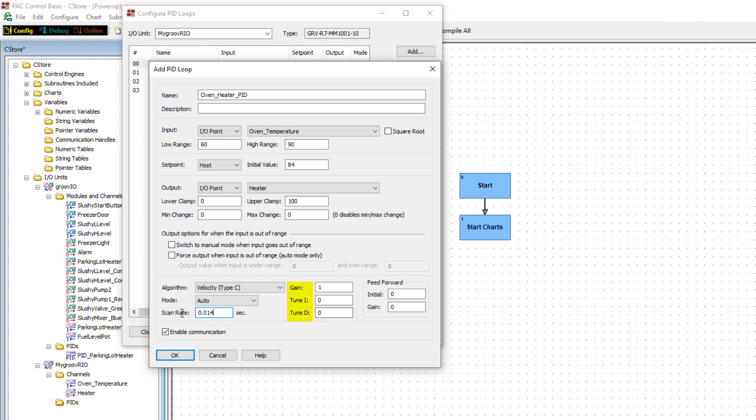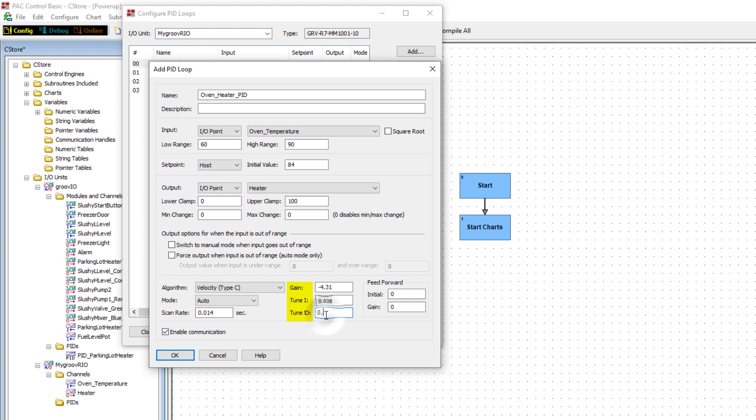Going through the PID tuning demo will also help you arrive at the ideal gain, that's the P term, I, and D terms. Enter negative 4.31 for gain, 0.028 for the I term, and 0.007 for the D term. We won't set the feedforward or feedgain parameters, but they're constants that are added and multiplied to the PID output.